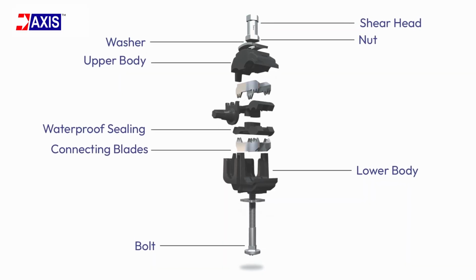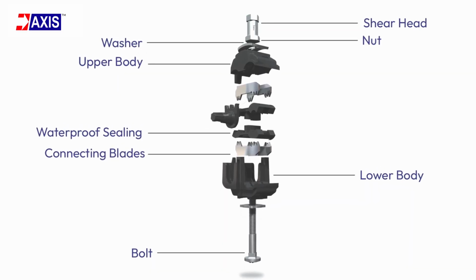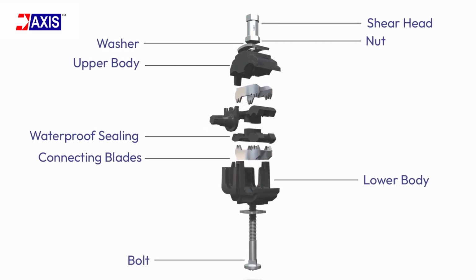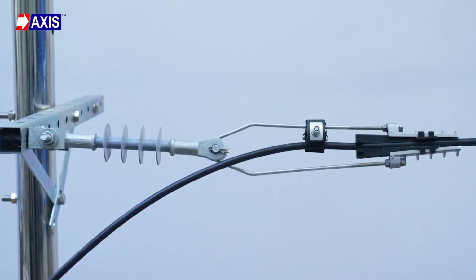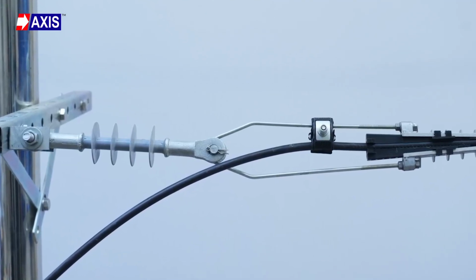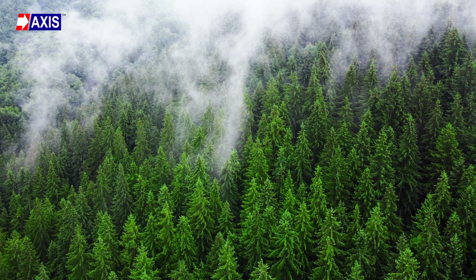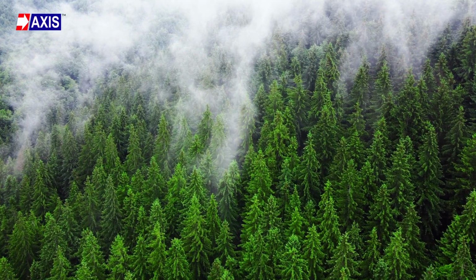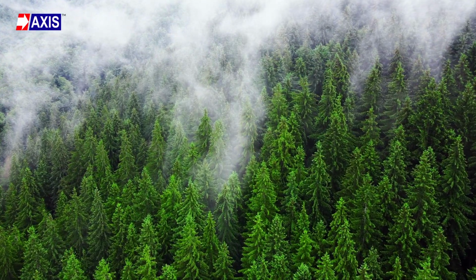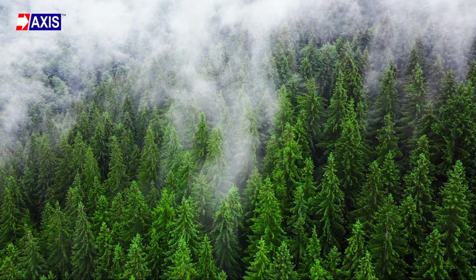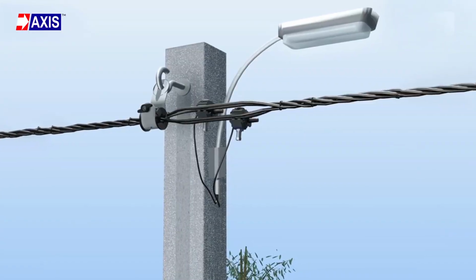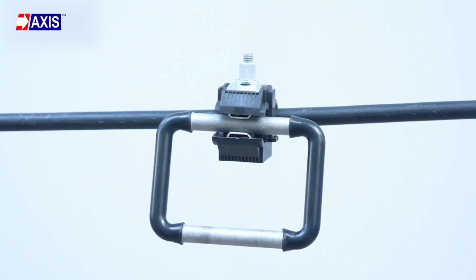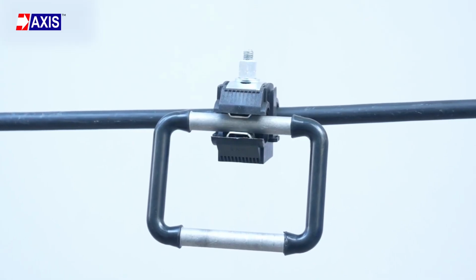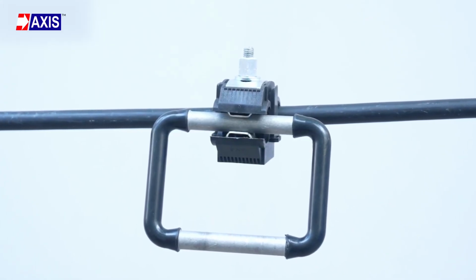An insulation piercing connector, or IPC, is used in medium voltage covered conductor systems to create a secure electrical connection without removing insulation. In hilly or forested regions, these lines are exposed to severe cold, snow, and frost. During such conditions, metal contracts and insulation hardens. If the connector cannot maintain proper contact, it will lead to arcing or failure.